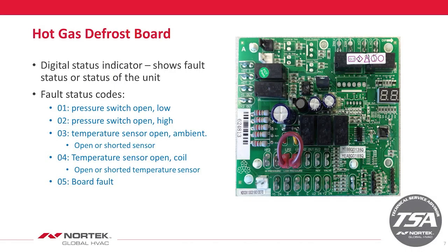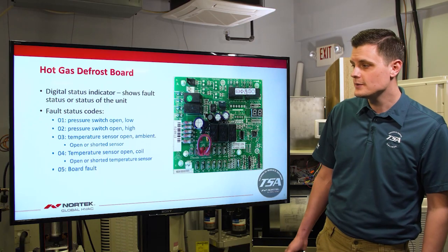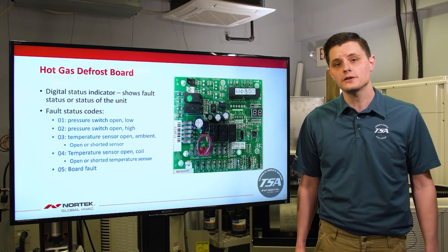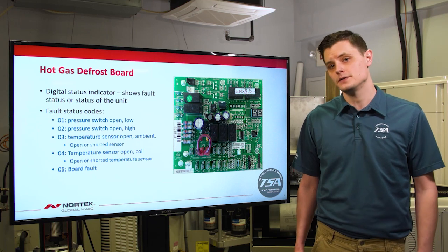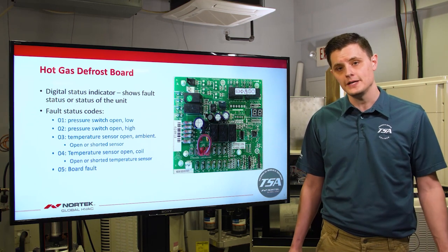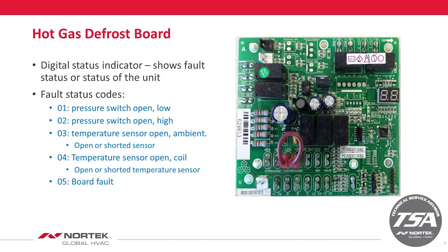There are up to five different fault codes on the board. Code 01 is your low pressure switch fault. Code O2 is a high pressure switch fault. Codes O3 and O4 revolve around the temperature sensors. O3 is your ambient sensor located in the control panel, and O4 is the coil sensor located at the bottom of the coil on the inside. An O5 code is a generic board fault — if you get an O5, you want to replace the defrost board.